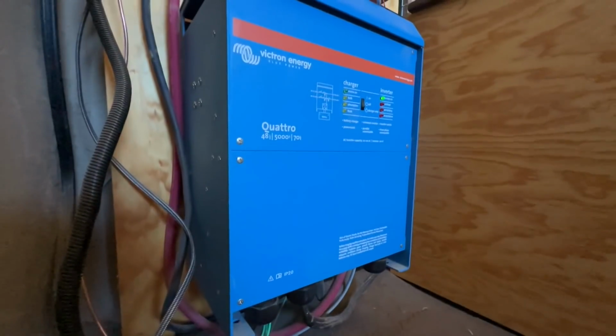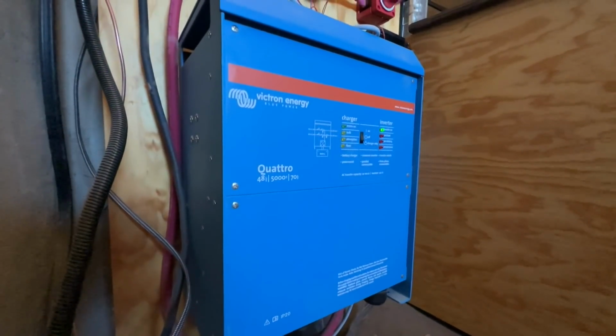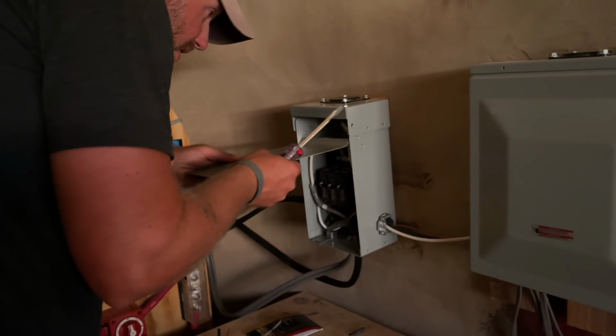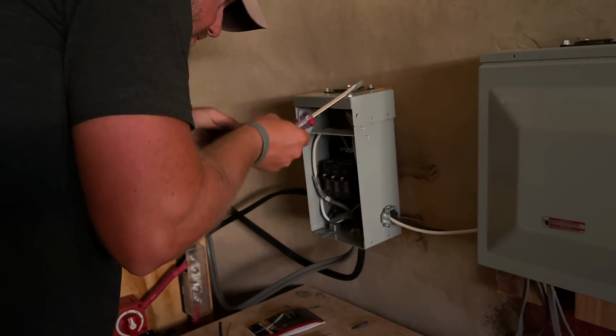First is the main wire that comes out of the inverter. You've got 120 volt power that has to go somewhere, so we opted for 6-2 wire. I know that's huge and probably overkill, but we're thinking ahead. If we ever go 240, or add another inverter, we don't want to have to pull wire back out of the ground and redo it all. You can only go through that service entrance so many times.